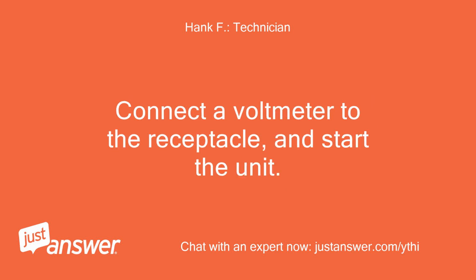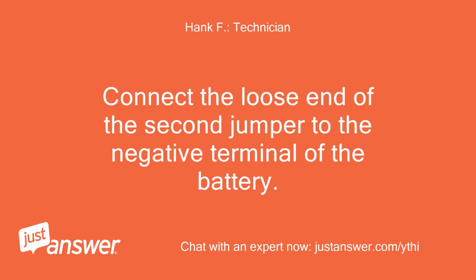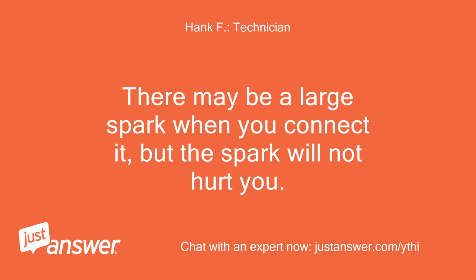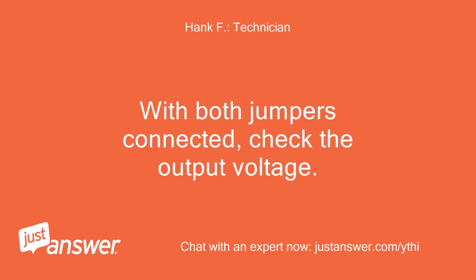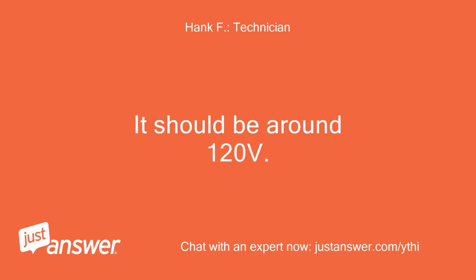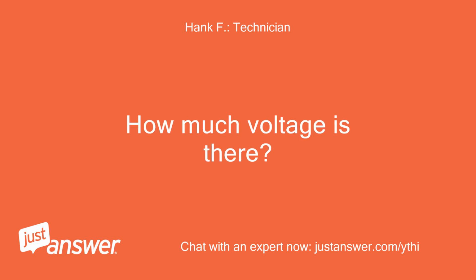Connect a voltmeter to the receptacle, and start the unit. Connect the loose end of the second jumper to the negative terminal of the battery. There may be a large spark when you connect it, but the spark will not hurt you. With both jumpers connected, check the output voltage. It should be around 120 volts. How much voltage is there?